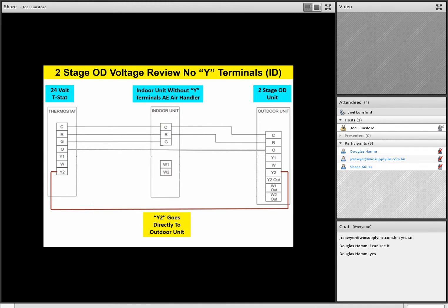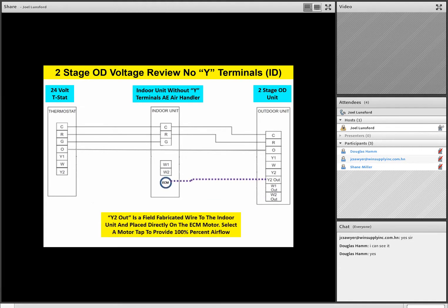Okay, so from the outdoor unit, we'll then take a W1 output and bring it to the indoor unit for our first stage auxiliary heat. W2 out from the outdoor unit comes in and hits W2 on the indoor unit, our second stage heat, a wire or pigtail. Now watch this, team. Y2 out from the outdoor unit comes in and goes directly to the ECM motor. Now this is a field fabricated wire. So if I take Y2 out from the outdoor unit, this is a field fabricated wire that the contractor will manufacture when he installs this, if he installs this on a two-stage unit outside. So he'll take Y2 out and bring it straight in.